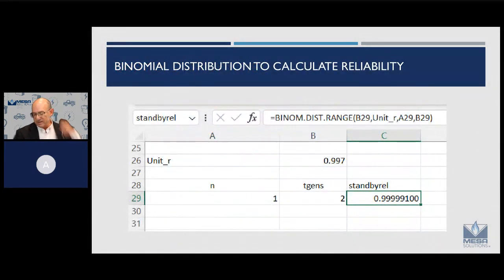And just to get a little deeper in the math for a short moment, one way you can model the reliability of the standby system, if you have N+1 or multiple units that add up to your N, is that Excel spreadsheets fortunately have this formula all set up for you, but it's the same calculation you may remember from a statistics class, where maybe the problem is: if you're going to flip 4 quarters, what's the probability that 3 of them will be heads?